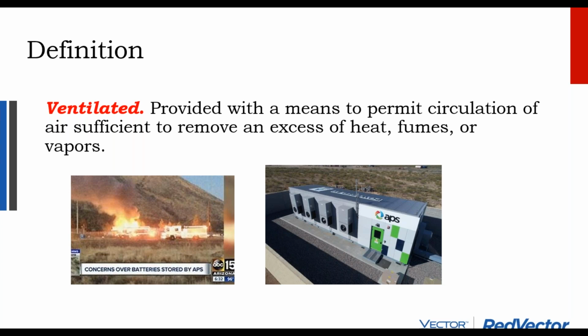No one died. I think one person had serious injuries, the fire chief who opened the door. And so what we're going to see is that as the sealed batteries get larger in size, the ventilation requirements become mandatory even with a sealed battery. So the takeaway from this is that you can't just assume that the battery room does not need to be ventilated simply because you have a sealed battery.